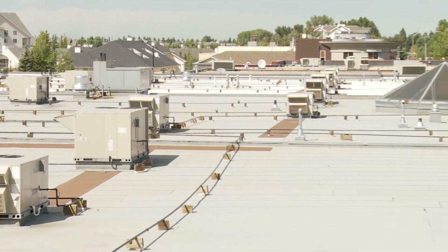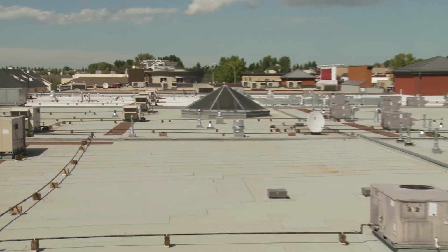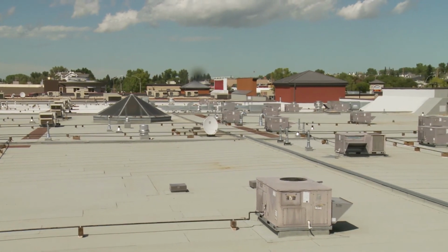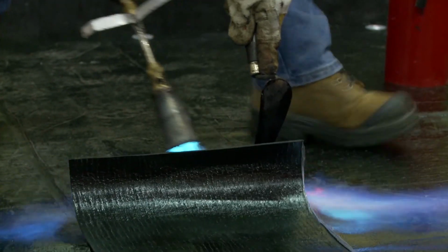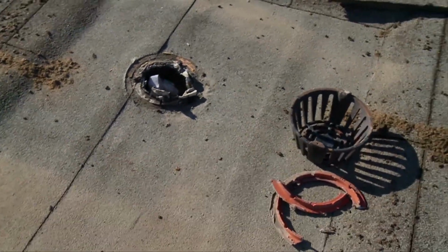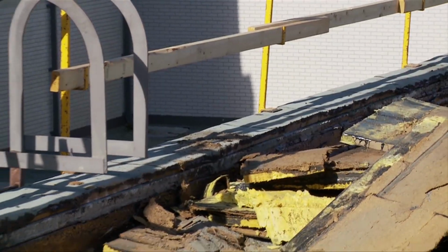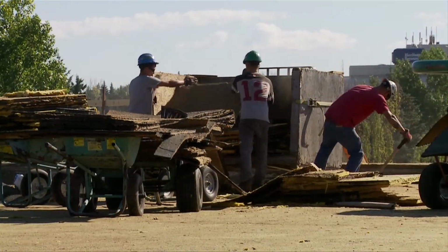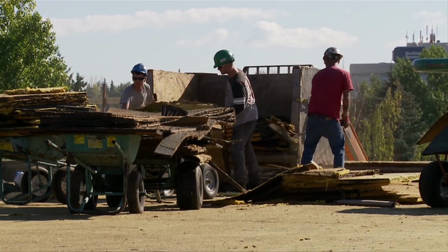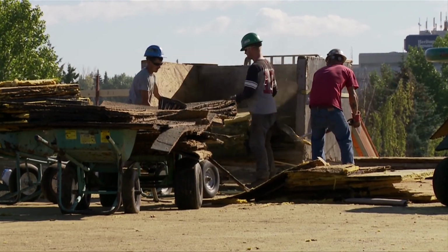In new construction, highly combustible or incompatible air barriers and building envelope substrates and materials may be incorporated. The design must provide for compatible materials for torch-adhered, modified bitumen products. Roof and wall penetrations are not often sealed to prevent or retard flame migration. Poor housekeeping practices during the construction phase, such as accumulation of wood shavings or garbage disposal into the wall cavities by other trades.